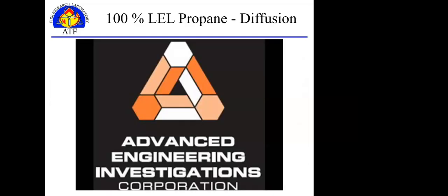So here are some videos that a former employer of mine put together, the guys at Advanced Engineering Investigations, or AEI. This goes through a couple of different minor or small explosions with propane, looking at both how much we are at the LEL, and how the mixing is done. In this case, they've just dumped propane into this little compartment and allowed it to mix naturally through diffusion.